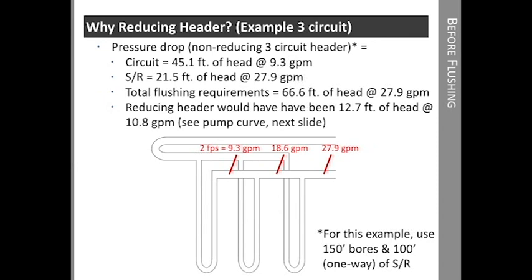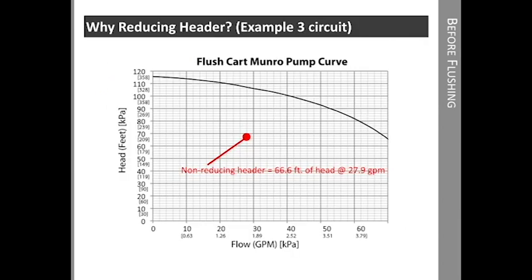Let's take a look at how the two designs compare on our flush cart pump curve. In the case of the Munro pump, you can see that we can still purge air from the loop even if we don't reduce the header on a three circuit loop with three quarter inch circuits. Naturally, the reducing header would be even easier to flush. However, let's look at a larger ground loop.